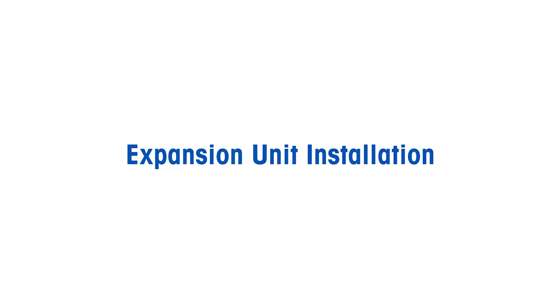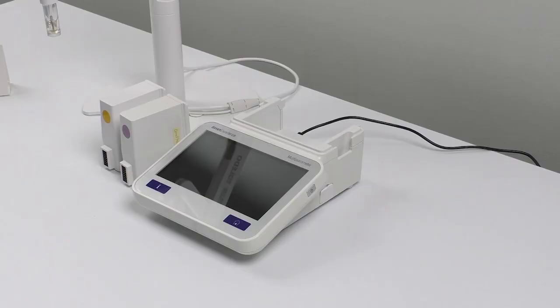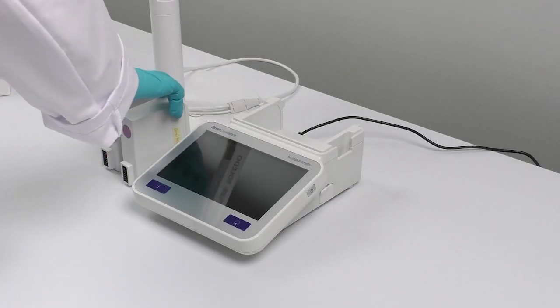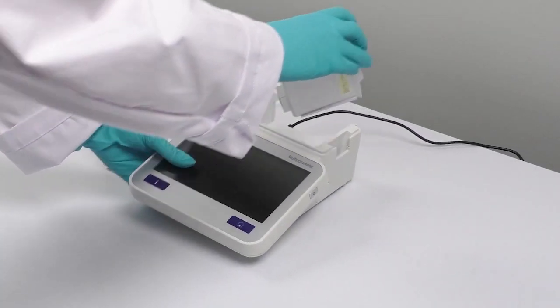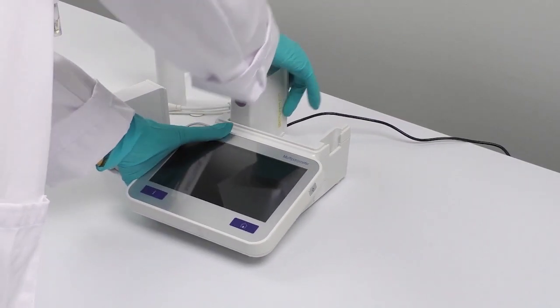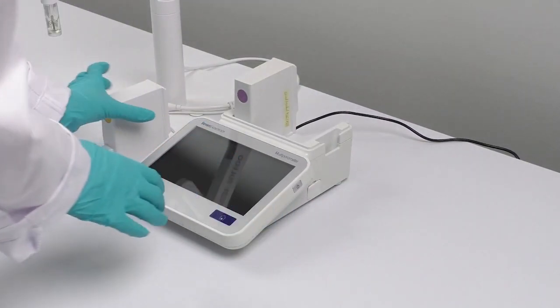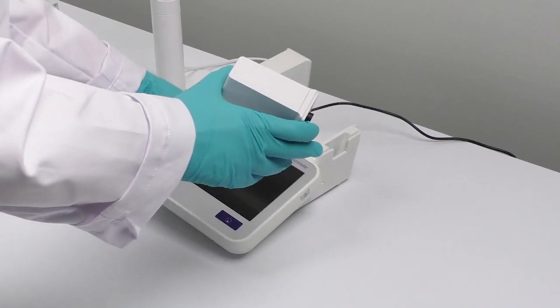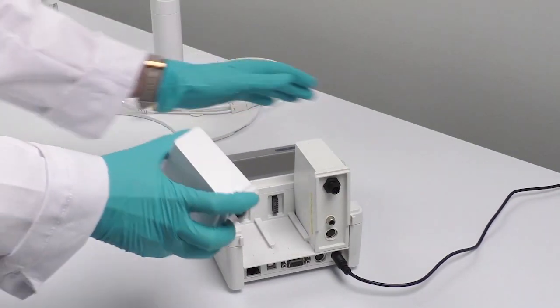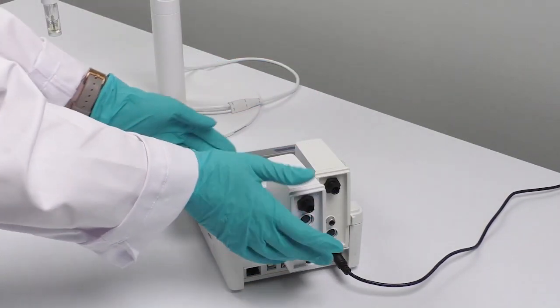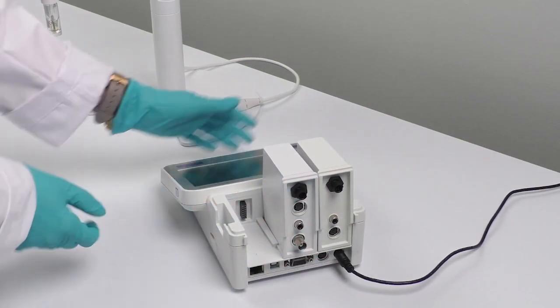Now, we show you how to install these expansion units. When installing the expansion units, it's important to insert them by sliding them through the rear part of the 7Excellence towards the front. When properly inserted, you should hear a click at the slot. Remember to always install modules when the 7Excellence is switched off.